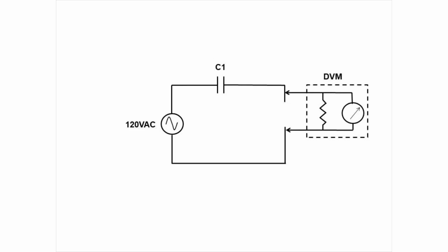In this voltage divider, just replace R1 with a capacitor and let R2 be the resistance of a digital voltmeter, and you will see the cause of the phantom voltage. C1 is capacitance, but it is not a component you wire into the power circuit. It's a capacitance that occurs naturally between bundled wires in home wiring. This capacitance acts in a complex manner, but for the purposes of this review, you can think of it as an AC resistor.